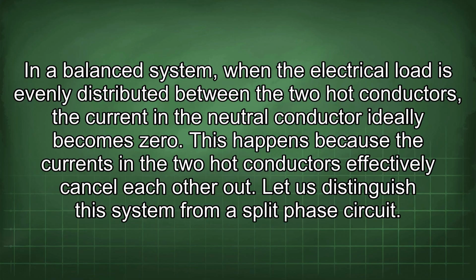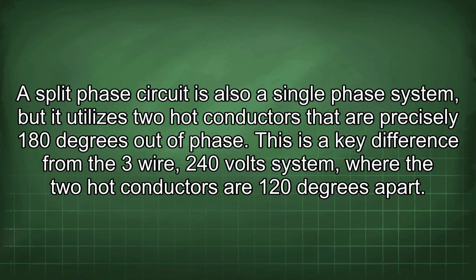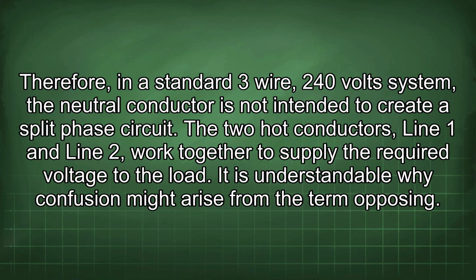Let us distinguish this system from a split-phase circuit. A split-phase circuit is also a single-phase system, but it utilizes 2 hot conductors that are precisely 180 degrees out of phase. This is the key difference from the 3-wire, 240-volt system, where the 2 hot conductors are 120 degrees apart. Therefore, in a standard 3-wire, 240-volt system, the neutral conductor is not intended to create a split-phase circuit. The 2 hot conductors, line 1 and line 2, work together to supply the required voltage to the load.